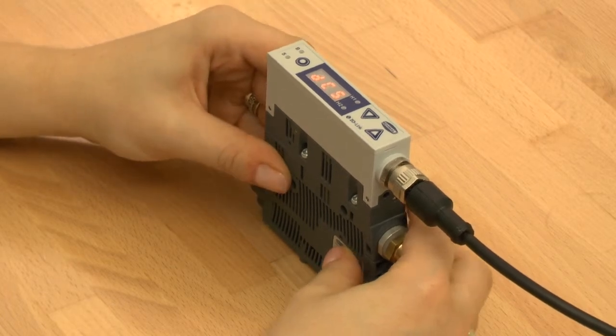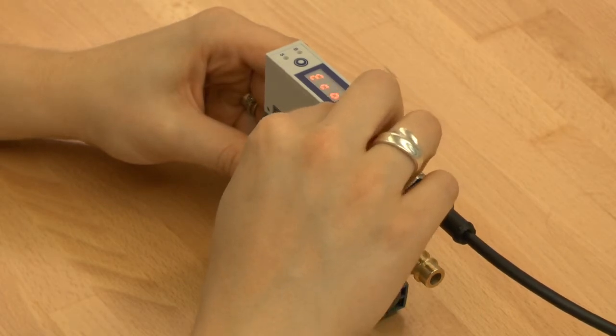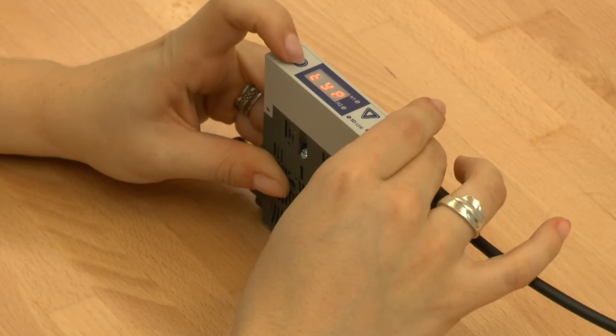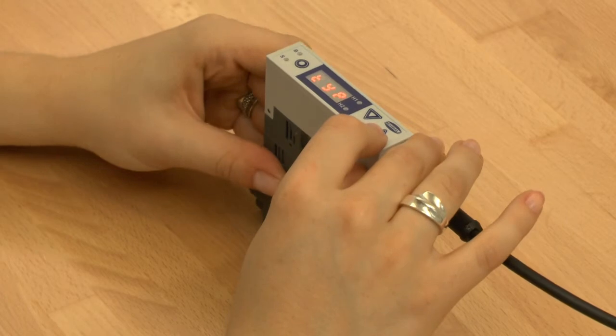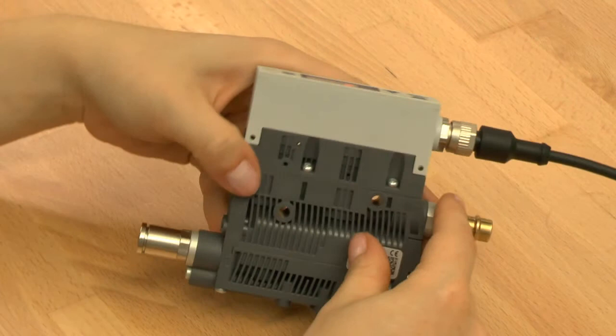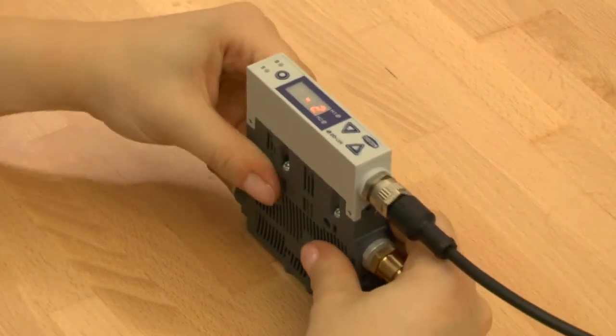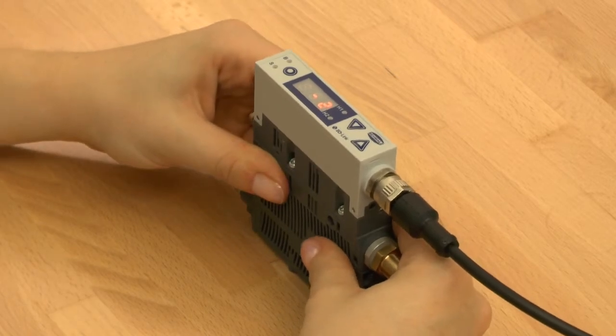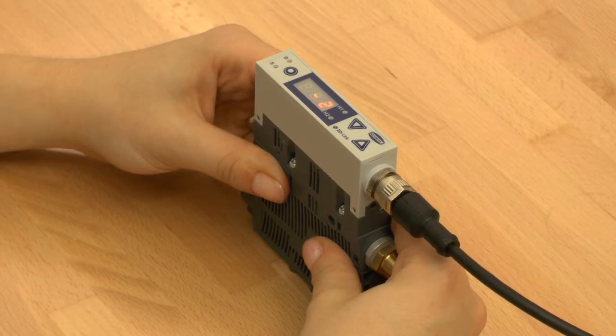Using the function type you can choose the output type PNP or NPN. The strength of the blow-off pulse can be adjusted by a throttle screw. If the ejector was wrongly programmed it can be set back into the factory settings. All switching points and configurations are reset to factory settings. The counters are not affected by this function.